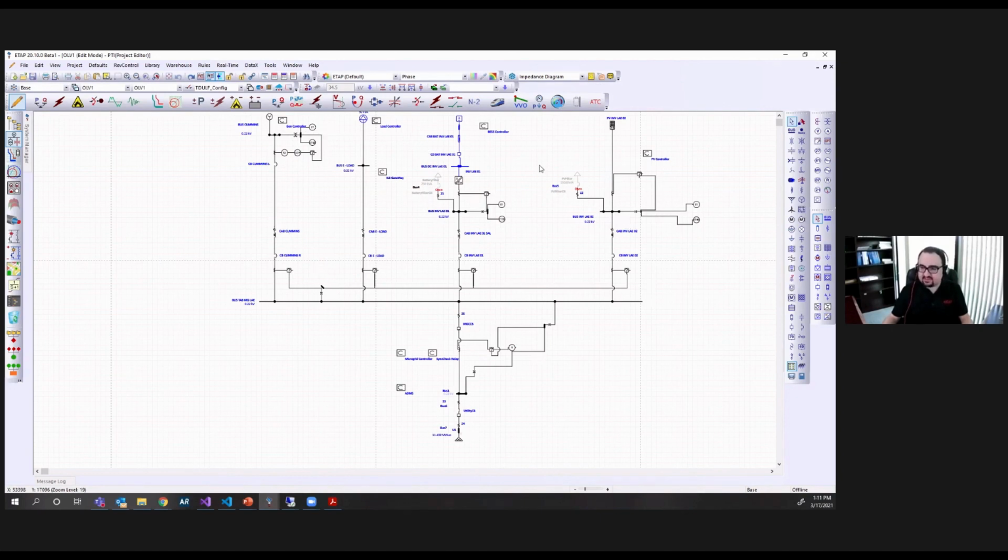Once we model the system, we can put in the primary controllers, as you can see: load control, BESS control, PV controller. Again, this is not a complex process. You can put in the primary controllers and do some simulations to validate the load flow and transient stability results before you apply the microgrid controller. Once the results are acceptable and validated, you can add the microgrid controller and do the analysis. It is a very easy and straightforward process, and we are providing several documents that explain each process.